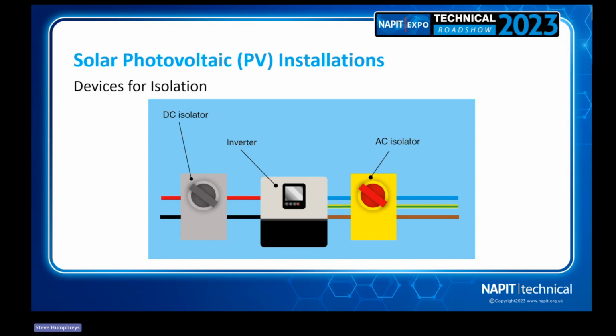And like I say, it's a bit of a noise in the industry at the minute. Some people, they are sometimes included on the inverter, but remember they still need to conform to 60947-3. So it can't just be a spurious inverter means of isolation and an isolating switch. So if it's included on the inverter, like I say, the consensus that's coming out quite a bit at the moment is that it's not required, and an external one's not required. But that is there from a point of safety, and actually some inverter manufacturers are not doing MC4 connections into the bottom of their inverter anymore.